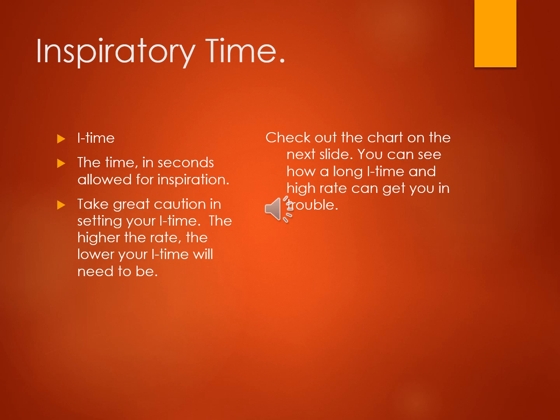But then if we go up to a rate of 20, 20 goes into 60 3 times. Now we have a 3 second cycle time. So that means if we said that same 1 second I time, we have 1 second going in and 2 seconds going out. So now you can see where that can start to have a little bit of problem. We need to be able to exhale, and our exhalation has to be longer or shorter based on the disease process.